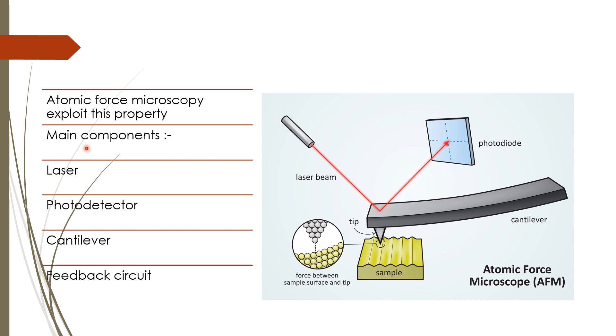The main components of an atomic force microscope involve a laser, photodetector, cantilever, and feedback circuit. The sample is scanned by a very sharp tip attached to a cantilever, and a laser beam is incident on the top of the cantilever. The reflection is recorded using a photodiode. As the tip scans the sample, it experiences forces and gets deflected. Because of these deflections, the light reflected from the cantilever changes direction and is recorded by the photodiode. Finally, a feedback circuit controls how far from the sample the tip will be scanning, and using this we take out the image of the surface.